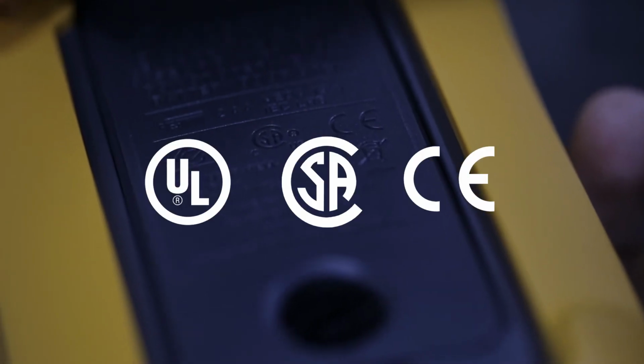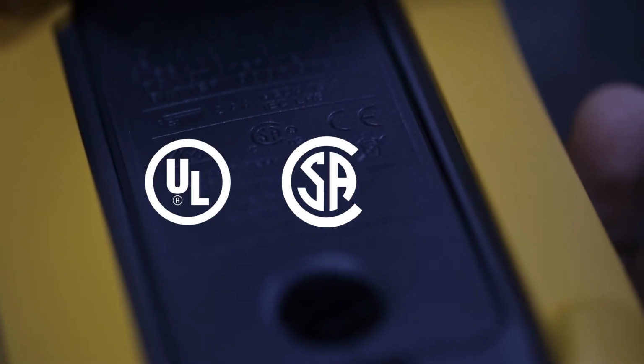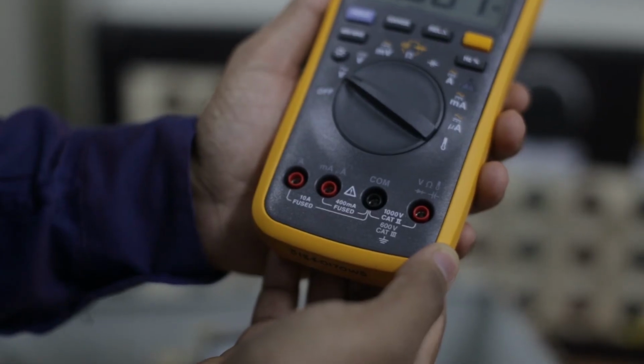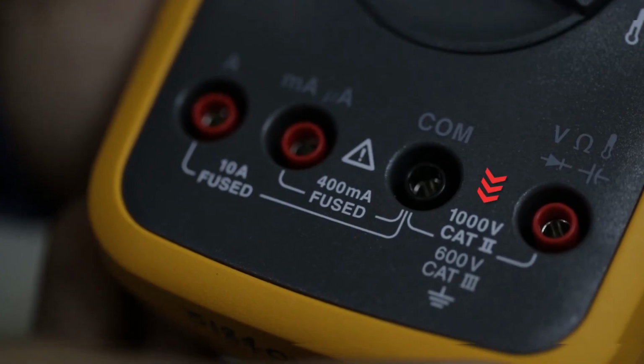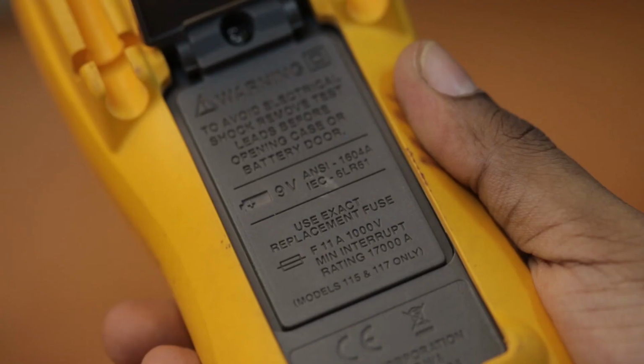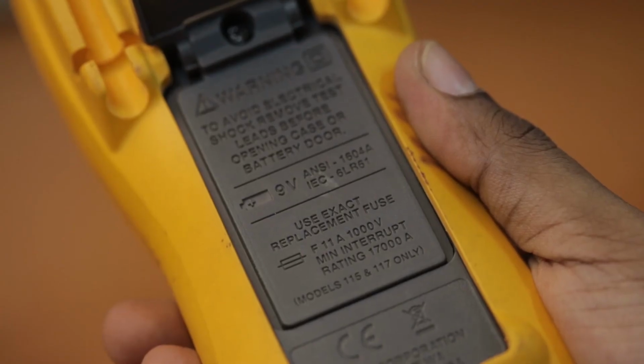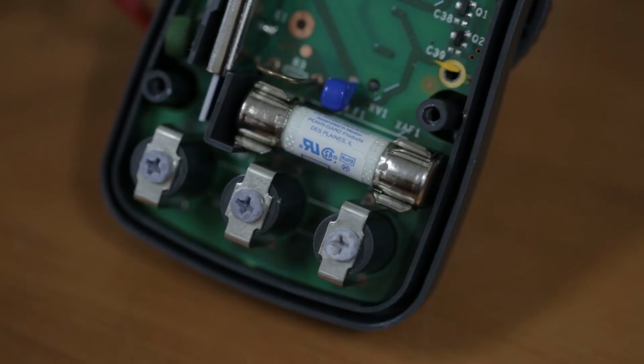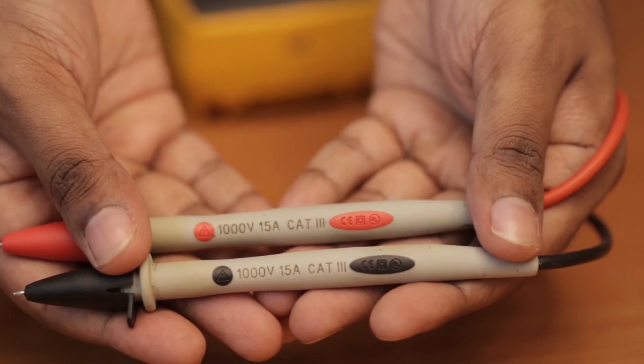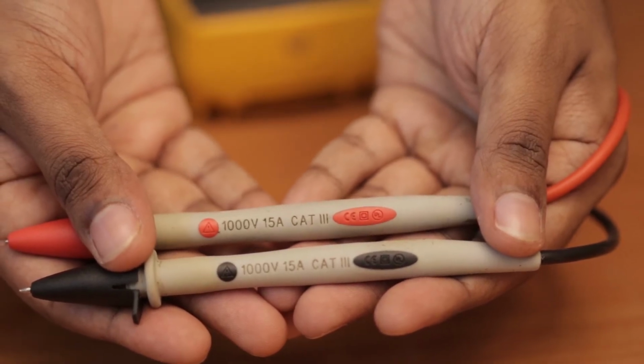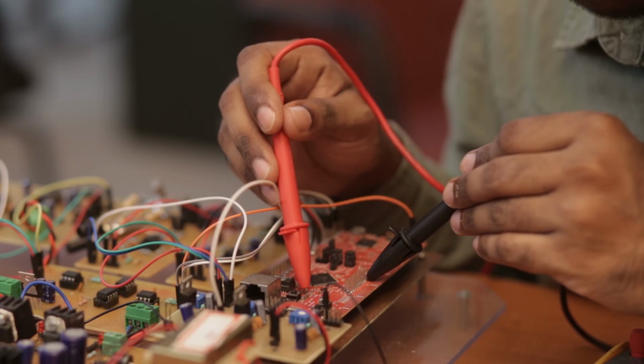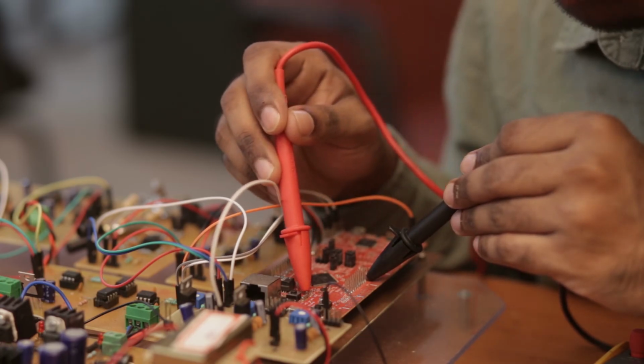The multimeter must have the symbol and listing number of an independent testing laboratory such as UL, CSA, TUV or other recognized approval agency. Always check the category rating and voltage rating of the meter before usage. Use replacement fuses approved by the manufacturer. Never replace a blown fuse with a wrong one. Test leads must be double insulated and with finger guards. When using the probe, keep your fingers behind the finger guards.